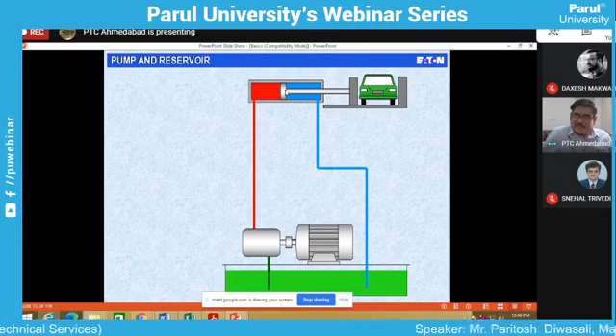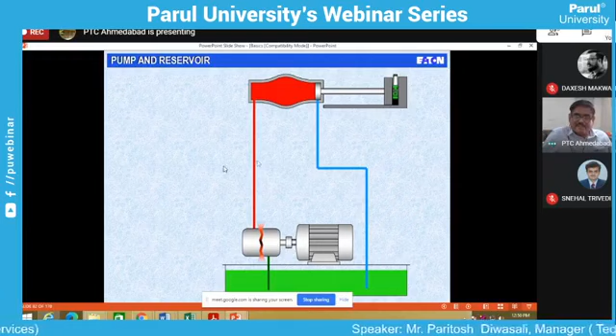Now I want to push this piston back. If I do not do that, what will happen? Tremendous pressure will be generated, and finally I will end up with a failure of the system, as you can see in this case. So a very fundamental requirement of any hydraulic system is to control the pressure generated within the confined or closed loop system. And for that purpose, we have a valve which is known as a pressure relief valve.